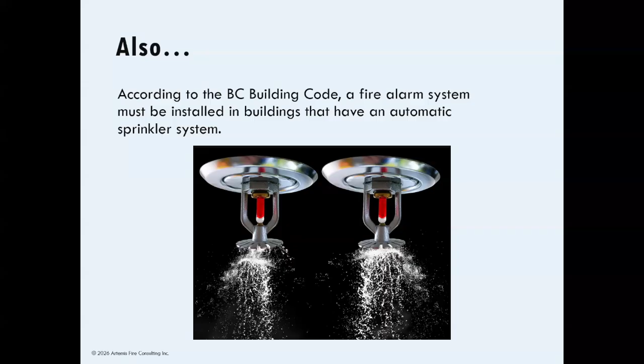Any building that doesn't have a sprinkler system but meets the requirements listed above. I have cherry-picked just the ones that apply to residential buildings, but there is a longer list of who is required to have a fire alarm system. A fire alarm system is also required in any building with an automatic sprinkler system. So whether you have a wet system, meaning the pipes have water in them all the time, or a dry system where the pipes are filled with air until water is released when the system is tripped. This is because we have to have a way to monitor sprinklers for non-emergency water flow, and when they are activated in an emergency, a way to notify everyone in the building that a sprinkler head is releasing water.